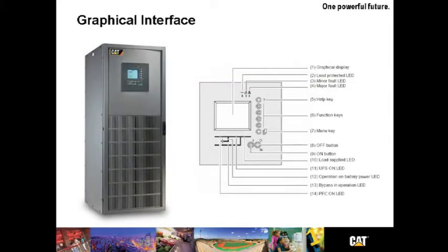Taking a closer look at the graphical interface, the UPS can communicate in 18 different languages, stores 2,500 time-stamped events, allows the operator to view statistical information about the UPS and its operation from the front screen. Communication interfaces include Modbus, RS-232, or RS-485 using the JBus protocol, or SNMP.